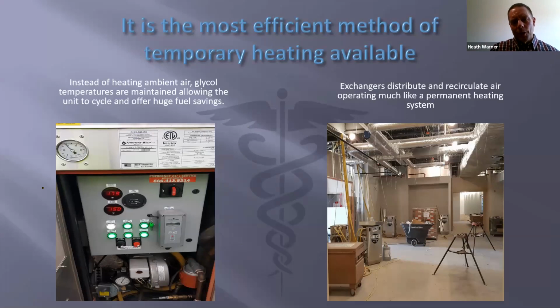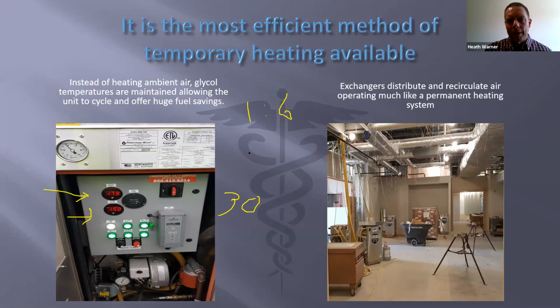So instead of having an open flame that has to operate 24 hours, 7 days a week, whether or not it creates heat, hydronics actually have set points and supply and return temperatures. If the temperature differential between supply and return isn't more than 30 degrees Fahrenheit, this entire unit shuts off. Furthermore, the exchangers that sit inside the work area have individual thermostats, which can be set to any temperature that you want. Glycol can pass unused by the coil and come back here. Consequently, a hydronic system is probably going to only operate about 1/6 to 1/8 of the time, depending on the actual R value and how closed off your building is, which saves a tremendous amount of fuel.